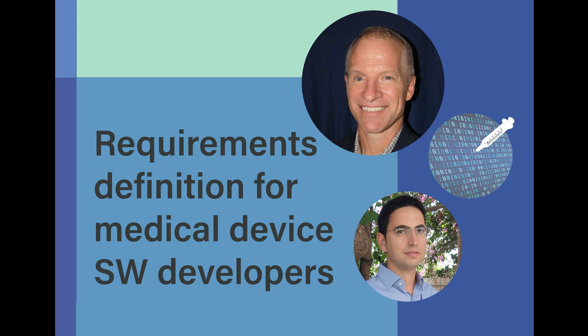So we may not end up with a hardware requirement specification. It could be the system requirement goes straight to an electrical design spec, and that's it. That's the only document they need. Maybe a mechanical materials specification or something like that. But on the software side, that system requirement is going to trace down to a lot of software requirements necessary to achieve the 400 millimeters of mercury.